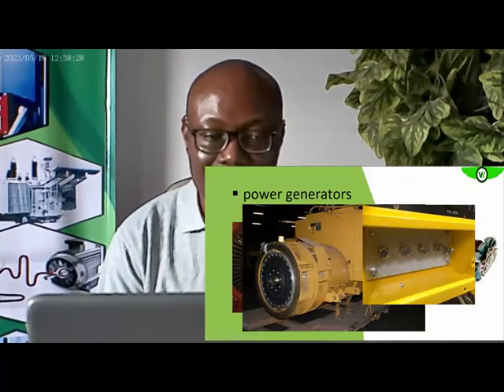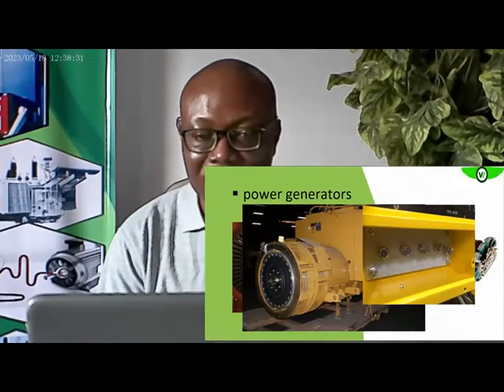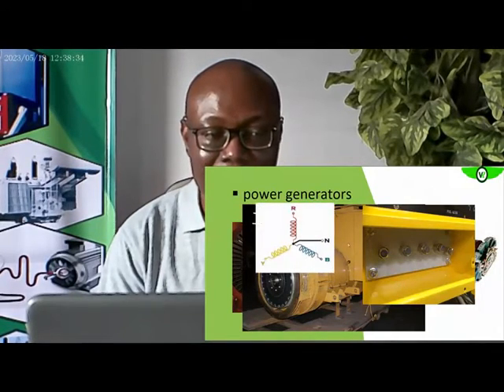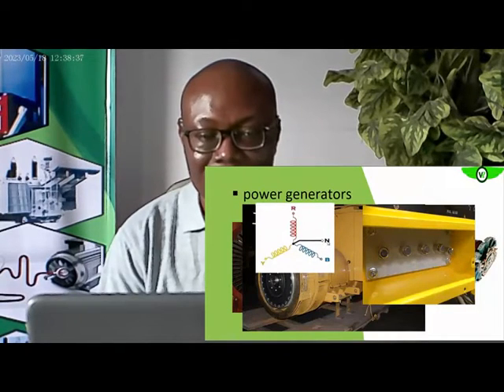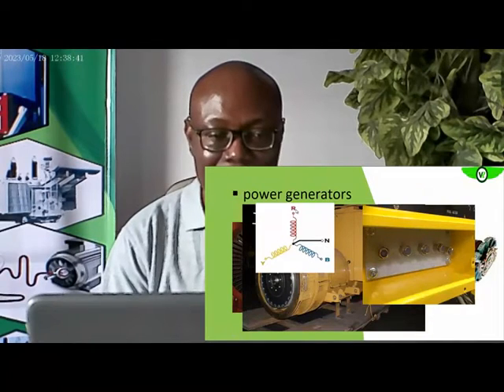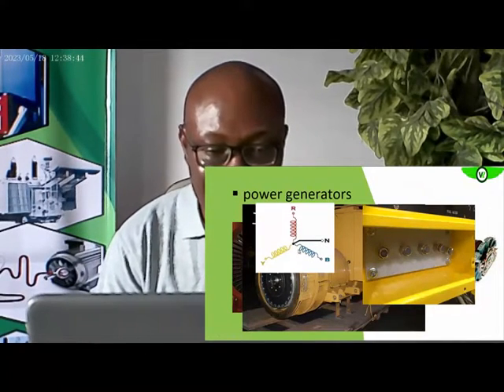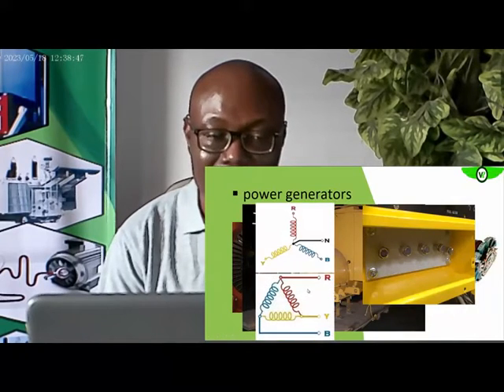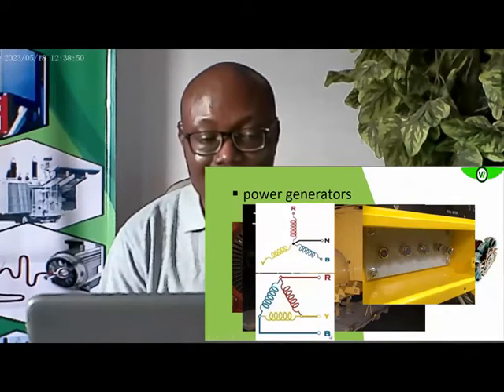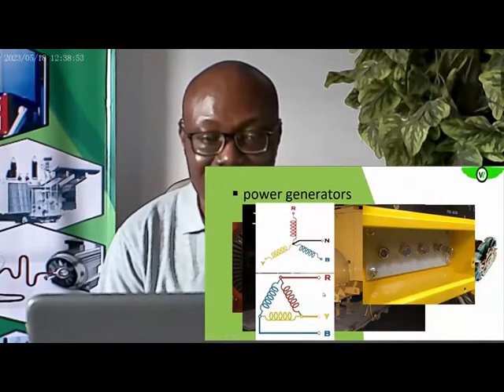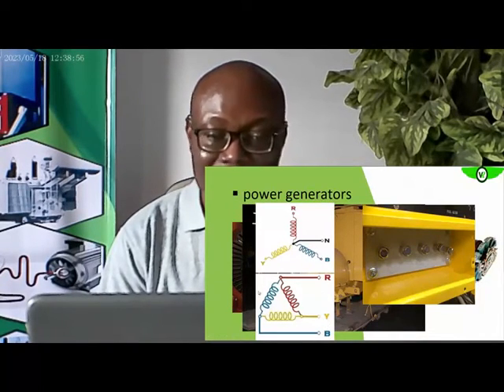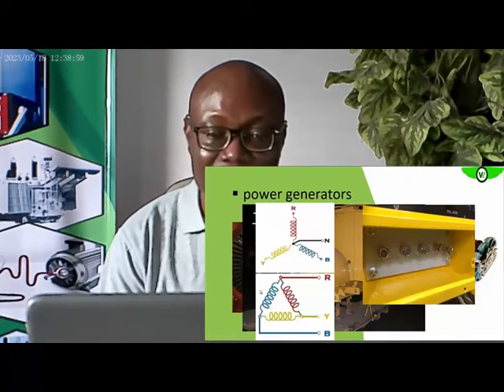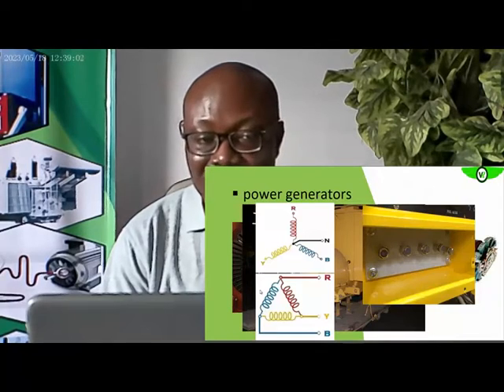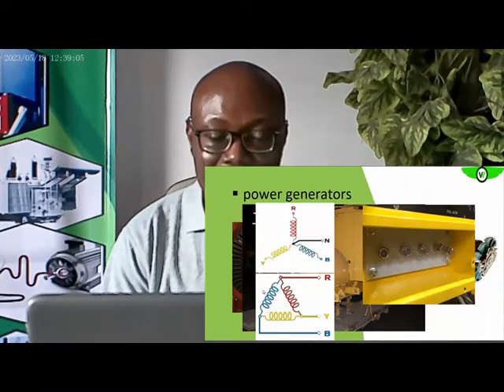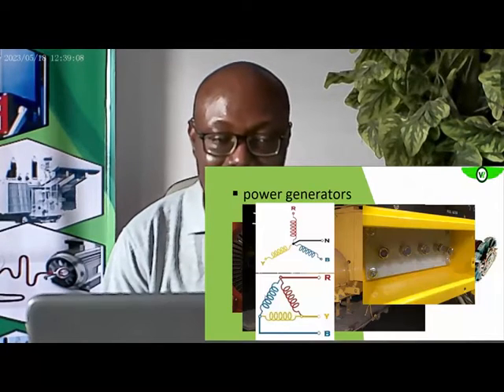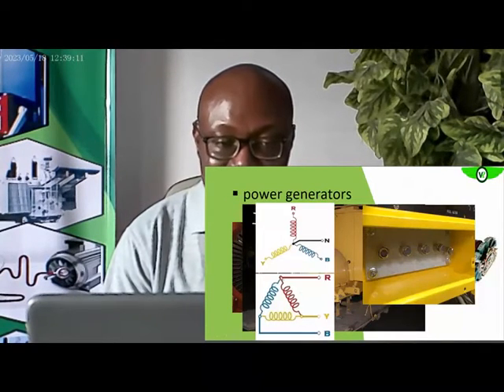So this is the connection of what we have here. This neutral point is this. Then we have line 1, line 2, line 3, the U, V, and W phase. This is when it is star connected. Of course, this one is now a delta connection. However the connection is in the generator, with the terminals you have here, you can only find insulation resistance to ground, except you have access to open up. If you can open up and disconnect the connection point or the star point, then you can test the insulation resistance of each winding.